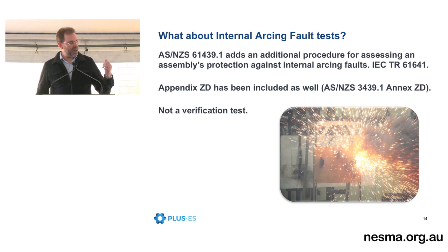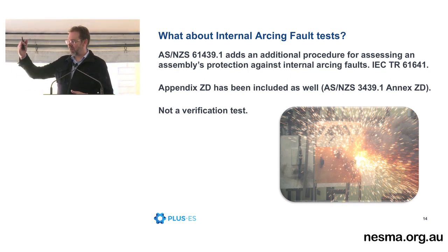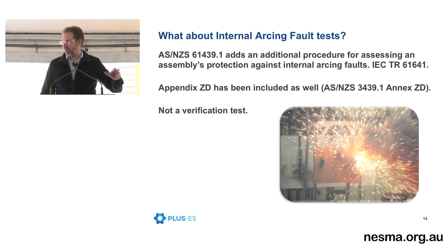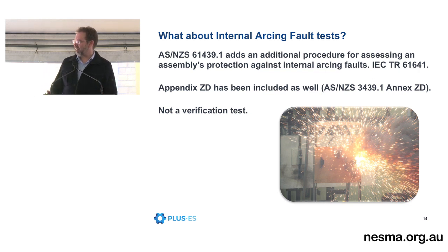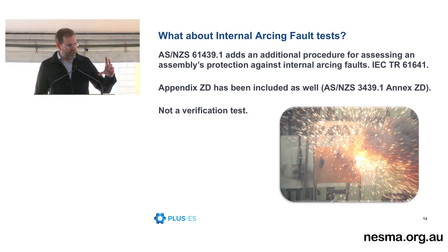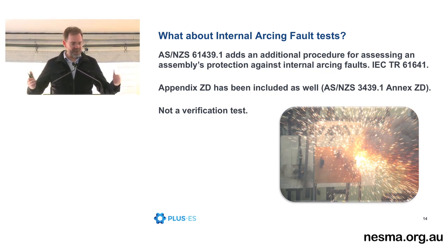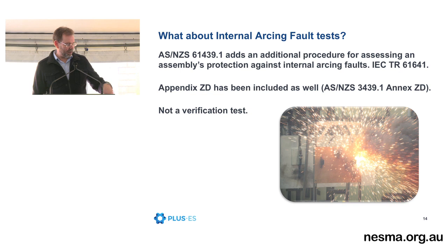I don't know if you recall, if you went into the test cell, we had the white cloth hanging down on one side, and on the other side we had the checkerboard pattern of black indicators. The checkerboard pattern is the indicator type for the IEC procedure, and the white cloth is the Australian indicator cloth. Basically we hang those cloths in front of the switchboards, and we do the arc fault, and one of the criteria, not all of it, but one of them, is that the hot stuff doesn't get out and set that white sheet on fire. And with the IEC, we've got the black indicators. They are positioned at the front of the board, but they're also on the sides and at the rear. So now we have a procedure for interrogating arc fault performance all around the switchgear. The AS was just positioned at the front.